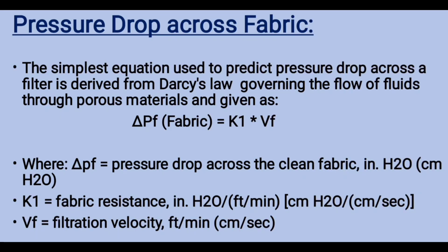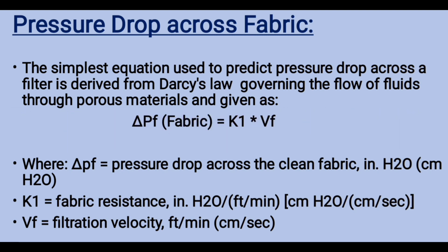Next, we will understand the pressure drop or delta P across the fabric. The simplest equation used to predict pressure drop across a filter is derived from Darcy's law, governing the flow of fluids through porous materials, and is given as: delta P_F = K1 × VF, where delta P_F is the pressure drop across the clean fabric, K1 is fabric resistance, and VF is filtration velocity.